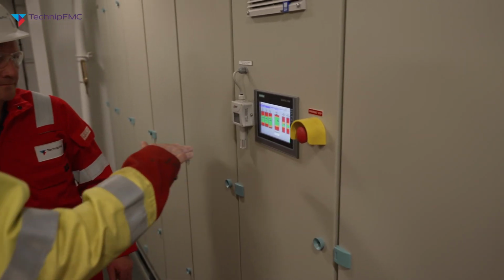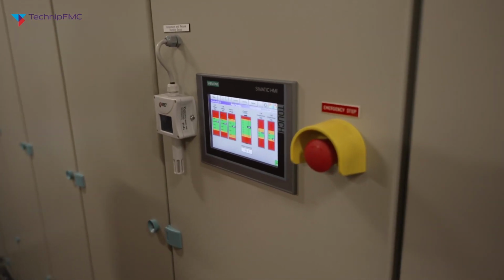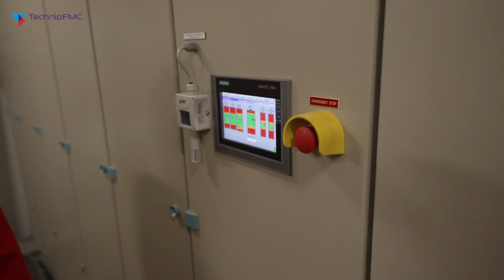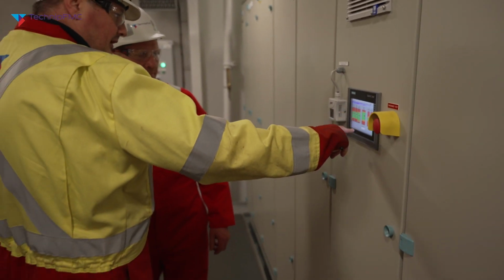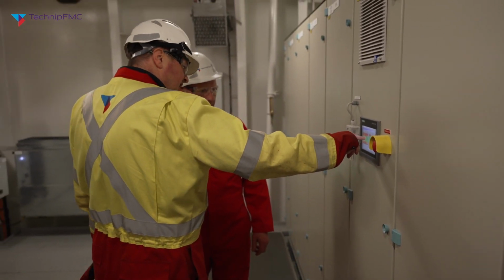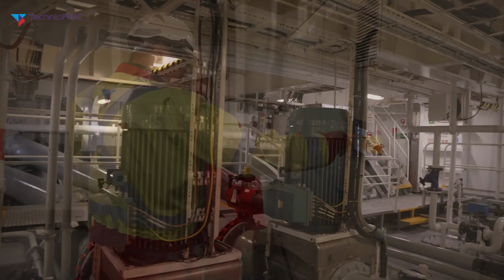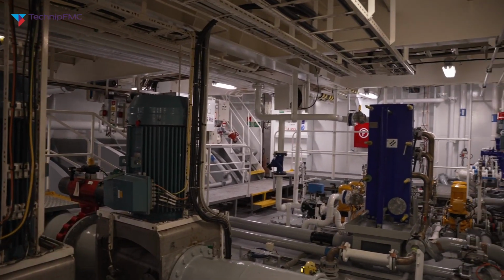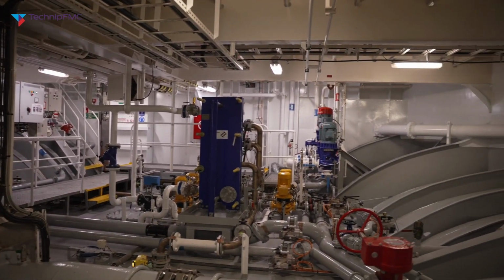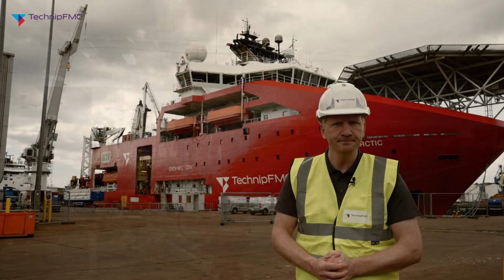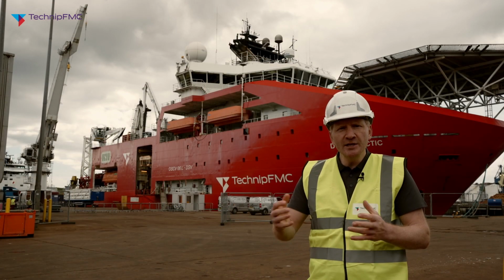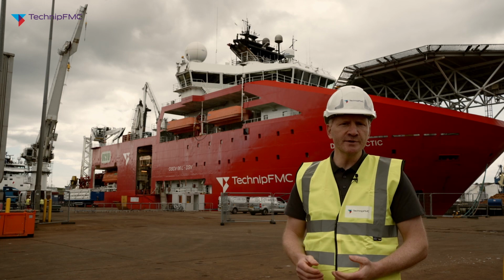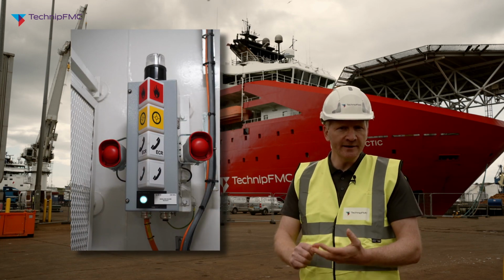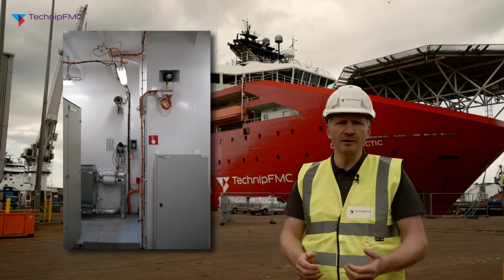It's important with lithium batteries to control the temperature, and we do that by pumping cooling water through the batteries themselves and also air conditioning the rooms that the batteries are in. That requires additional cooling systems - we have additional seawater, freshwater and chilled water cooling systems on board as well. Then we have the other ancillary systems needed in the battery rooms - fire detection, firefighting, CCTV, alarms, and so on.